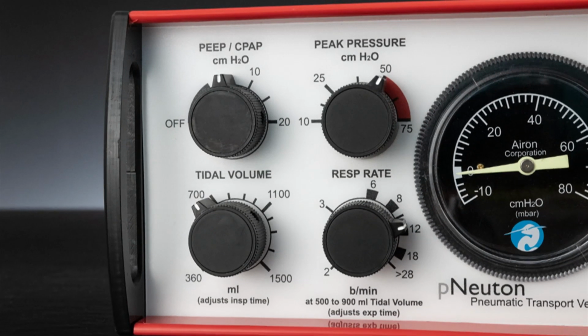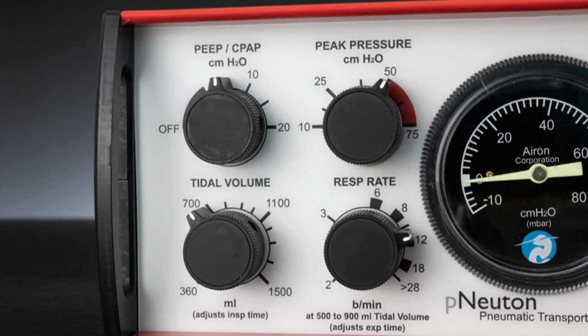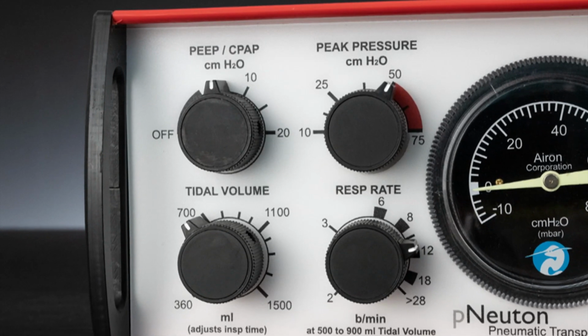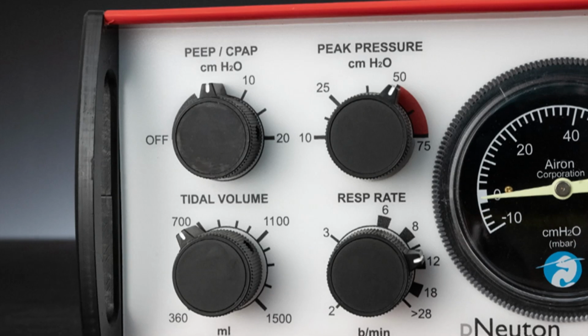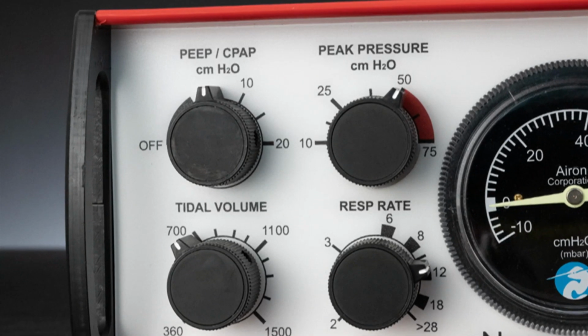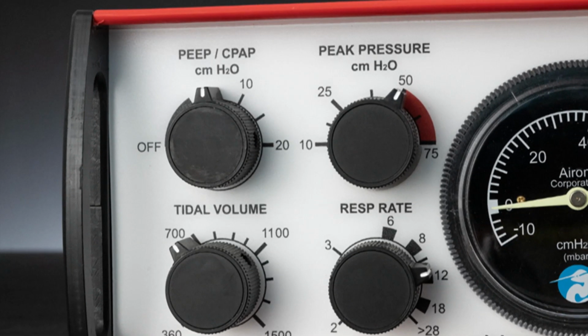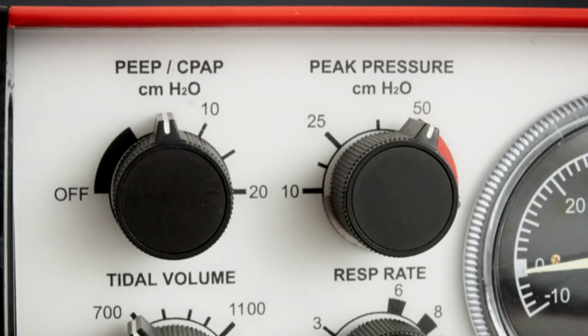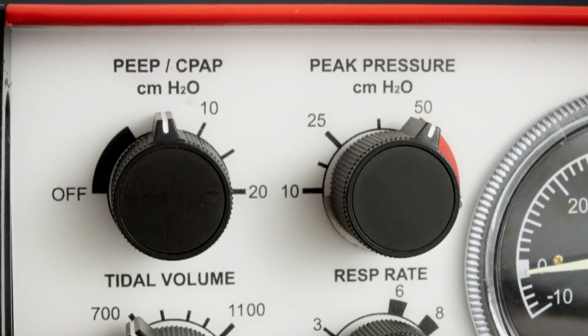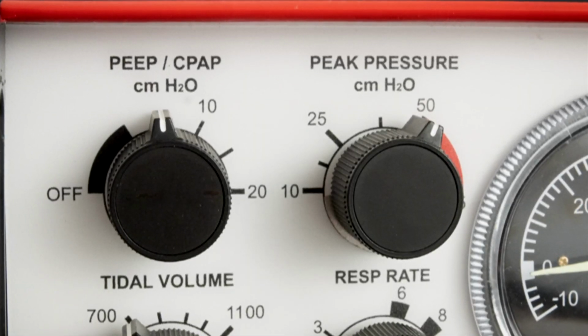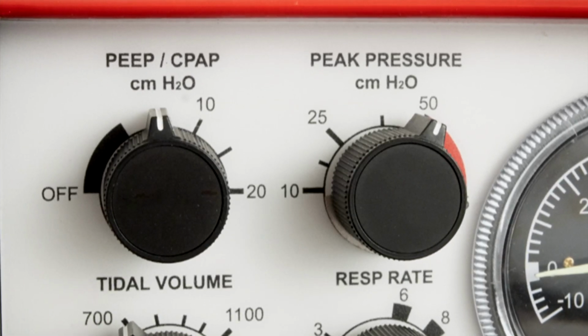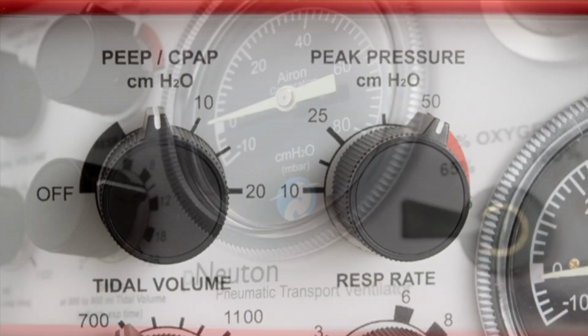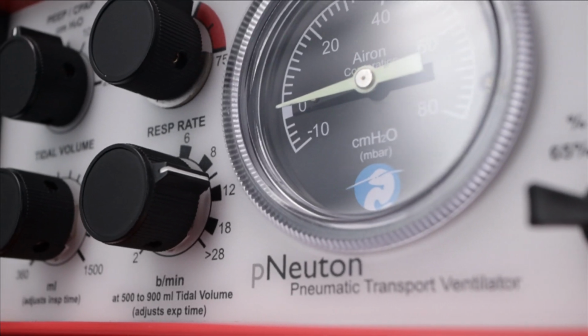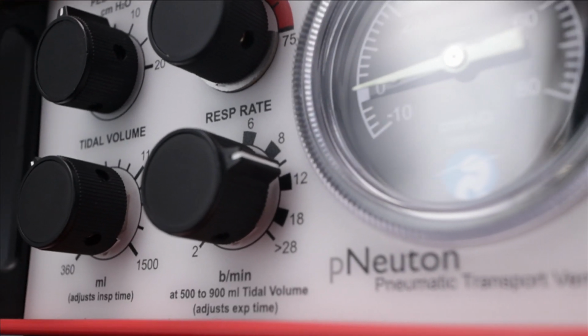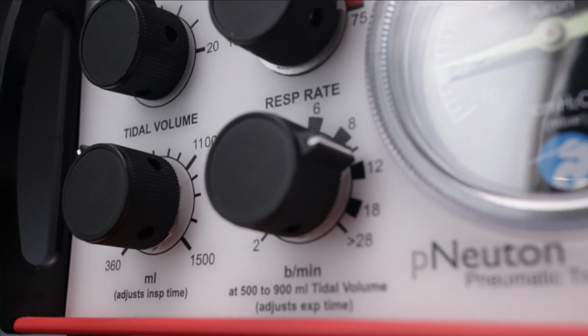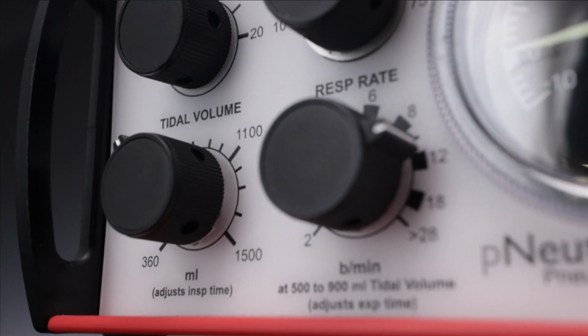In ventilation mode, set the pressure at a desired setting to assure patient safety, usually 10 centimeters of water greater than the delivery airway pressure, but please always use your organization's protocols. The peak pressure control can also be used to deliver pressure-limited breaths during pressure ventilation, with the CPAP PEEP control as the lower pressure setting. Tidal volume control. On the bottom left is the tidal volume control with a calibrated range of 360 to 1500 milliliters.